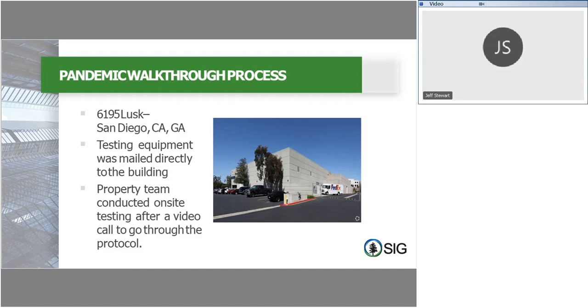This is a property managed by Healthpeak with administrative offices, and we mailed our testing equipment directly to the site. They didn't have a building automation system they could share a screen with, so during the walkthrough the engineering team conducted, I was on the phone with them discussing the measurements and making sure they followed the right protocols. We discussed how one of their rooftop units had no fresh air being brought in, and while still on the call, they diagnosed an issue with one of the fan belts that was causing no airflow. They got that fixed, retook the measurements, and confirmed proper airflow was restored.